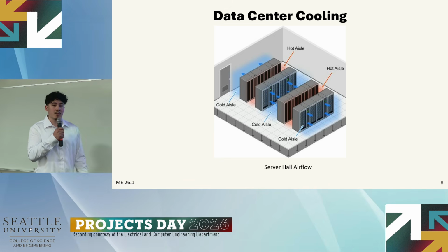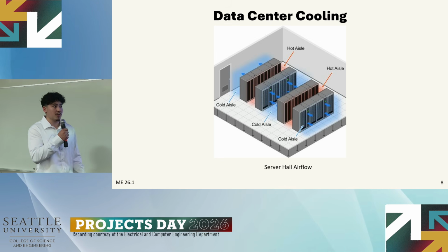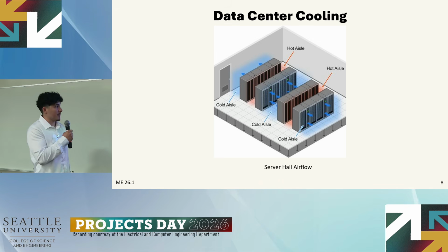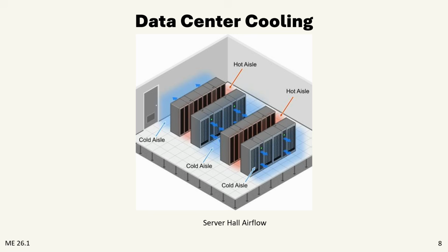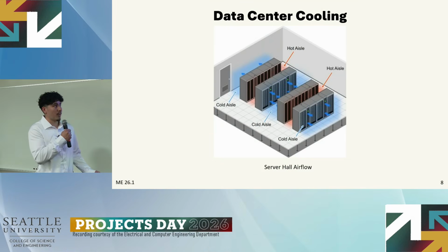Cooling takes a big part of the power load, which is why it's important that it runs efficiently. One of the main types of cooling used today in data centers is air cooling. Cold air is sent into the front of server racks, creating a cold aisle, as you can see in blue. Then when these servers are used, they expel heat out the back, creating a hot aisle, as you can see in red. This air is then exhausted to the outside, or it is recycled and reused in the cooling process. The reason this system is used is to prevent hot air from mixing with cold air so you can efficiently cool the air without needing more power.